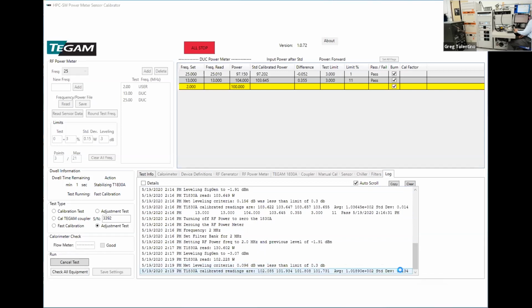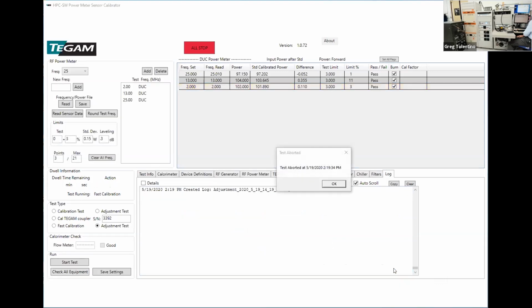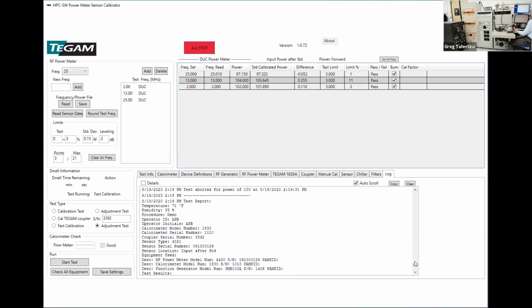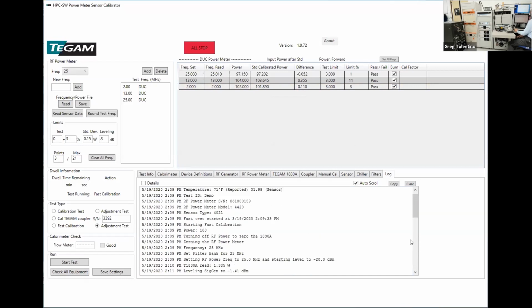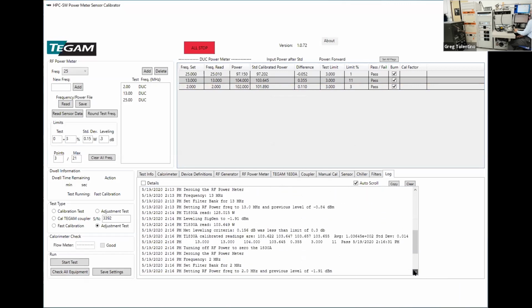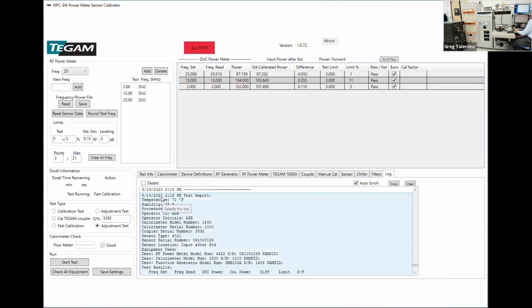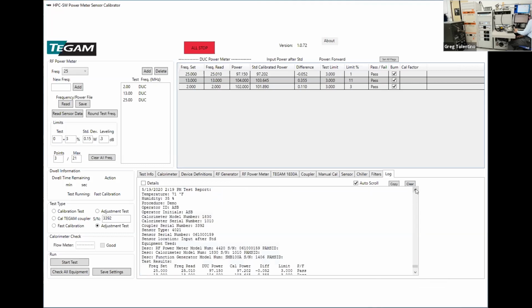Okay, we passed the standard deviation criteria, so it's going to go ahead and send the average to the Bird and tell it to do the calibration job. Okay, so it went ahead and did that. The test is completed. Okay, out of that, and then let's take a look at the log file that was generated. All the intermediate readings that were made are captured in the log, but at the end of the log we get a little summary of the lab conditions, the operator's initials, and what the standards' model number and serial number were. I'll scroll right there. There we go.